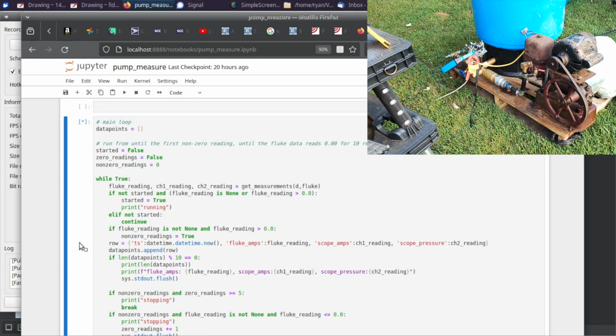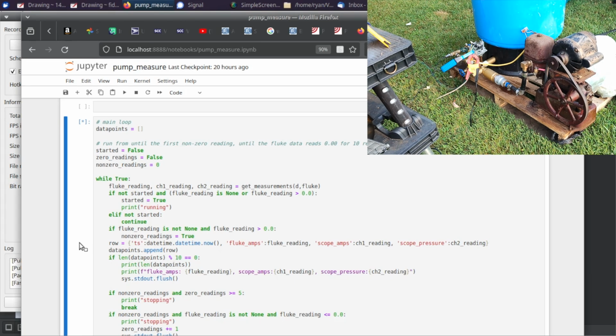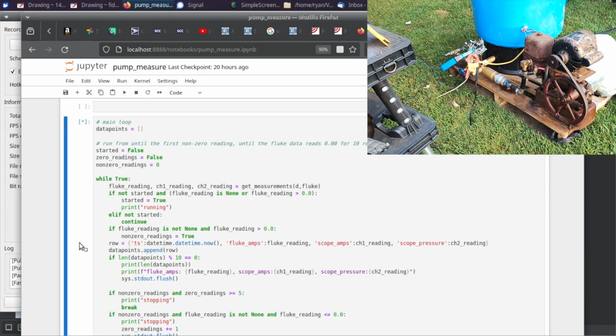All right, we're ready for data capture. I'm going to crack open that valve on the outlet hose, which just goes back to the supply tank, until we reach the cut-in pressure, and the capture is already running. So we're going to get a full cut-in to cut-out measurement. So we're just a couple psi above the cut-in pressure. We should reach it in a moment. I have pressure bleeding out the green hose there. The loop is running. I'm ready to look for that first non-zero current measurement.